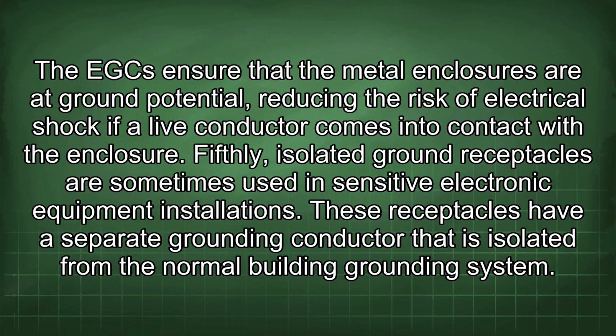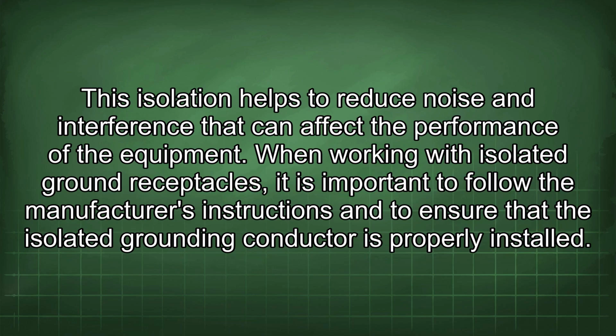Fifthly, isolated ground receptacles are sometimes used in sensitive electronic equipment installations. These receptacles have a separate grounding conductor that is isolated from the normal building grounding system. This isolation helps to reduce noise and interference that can affect the performance of the equipment. When working with isolated ground receptacles, it is important to follow the manufacturer's instructions and to ensure that the isolated grounding conductor is properly installed.